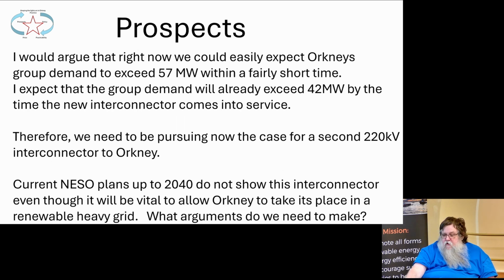I would argue that right now we could easily expect Orkney's group demand to exceed 57 megawatts within a fairly short time, and I expect that it will already be above 42 megawatts by the time the new interconnector comes into service. What I'm saying is that the changes that are occurring now are already pushing Orkney outside of P28's limit of 35 megawatts that we have.